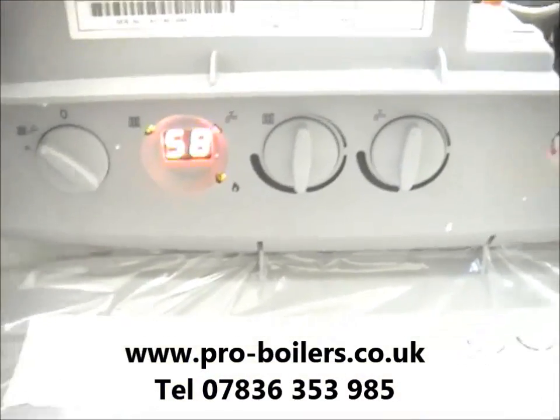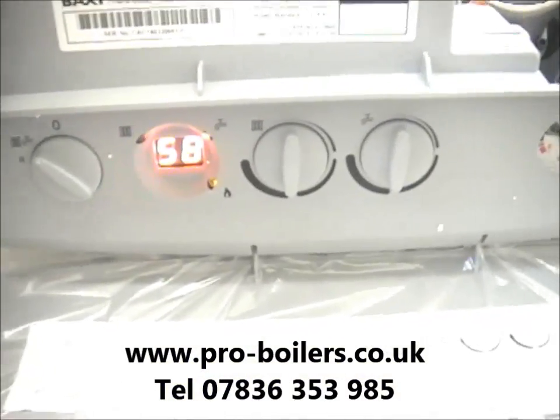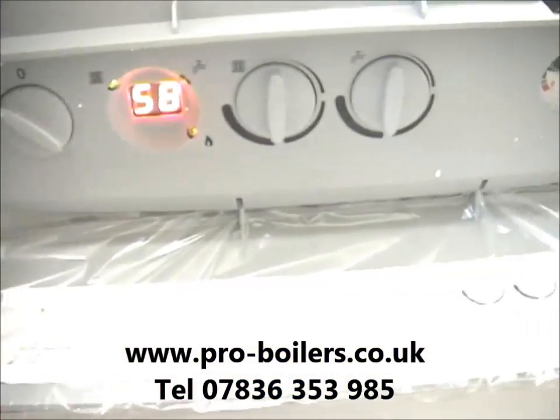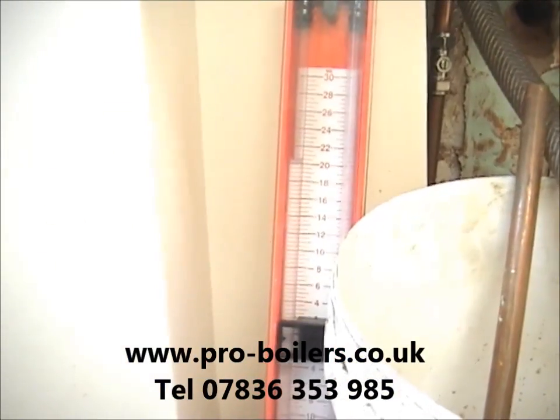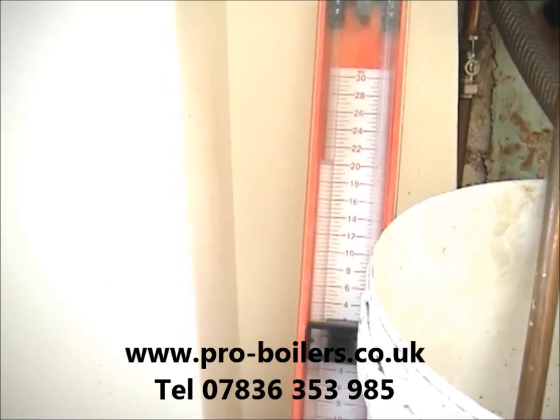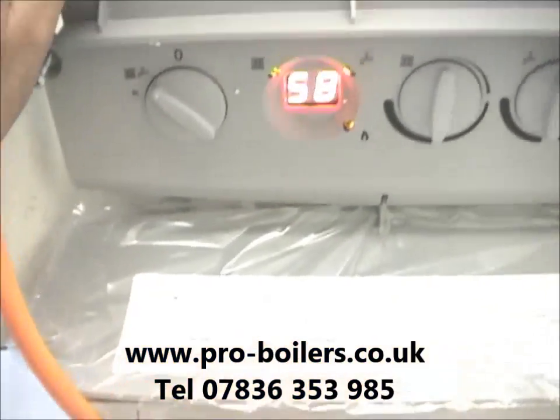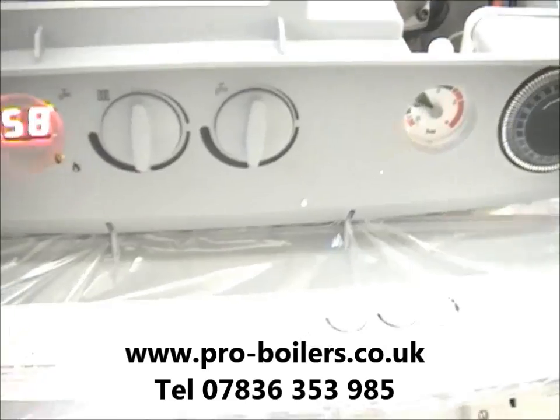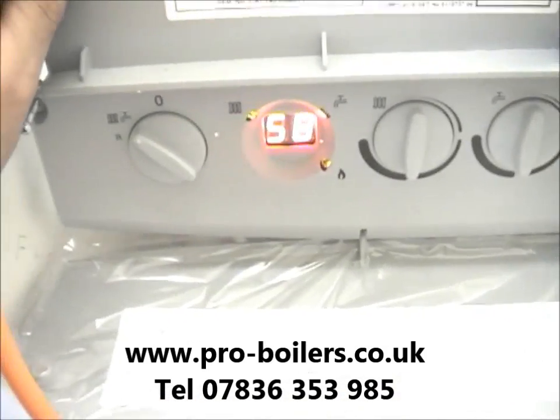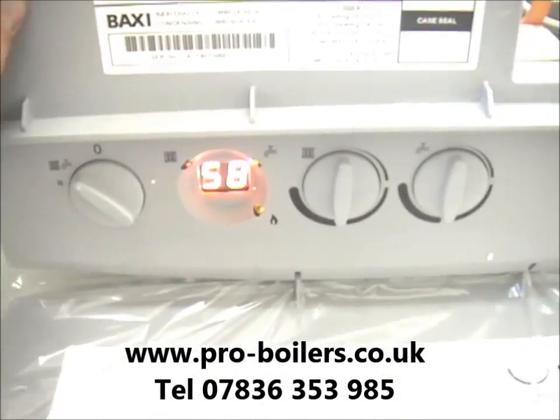Barry, Pro Boilers. We're just checking the inlet working pressure now. Fantastic, we've got an inlet working pressure of just over 20 millibars, about 21 millibars actually, and we've got it on calibration mode, so it's got a great gas supply. We'll carry on with the rest of it.